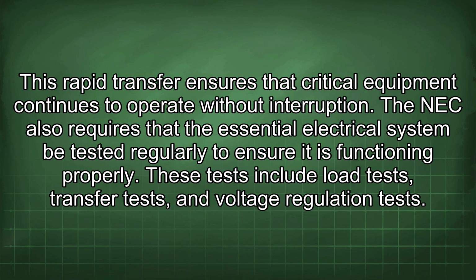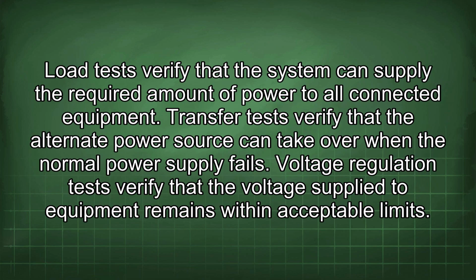These tests include load tests, transfer tests, and voltage regulation tests. Load tests verify that the system can supply the required amount of power to all connected equipment. Transfer tests verify that the alternate power source can take over when the normal power supply fails. Voltage regulation tests verify that the voltage supplied to equipment remains within acceptable limits.